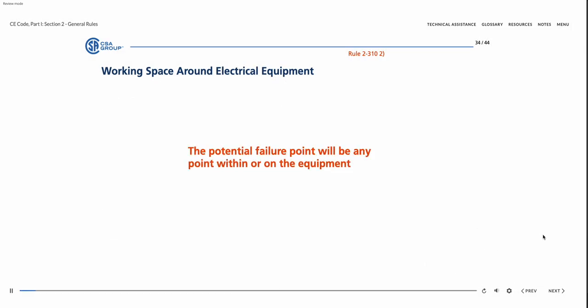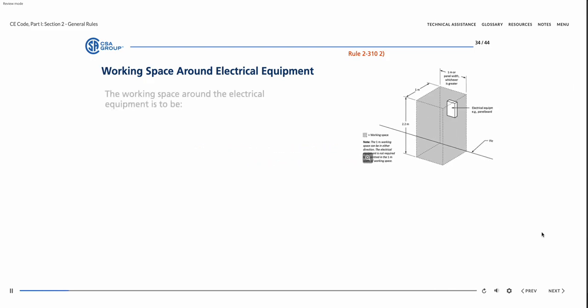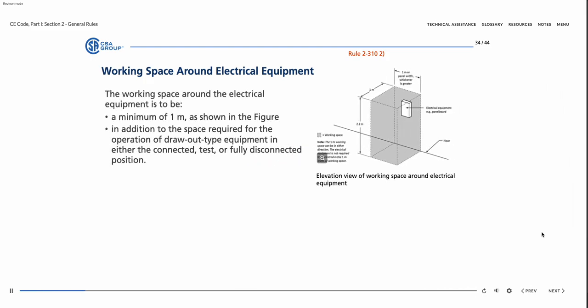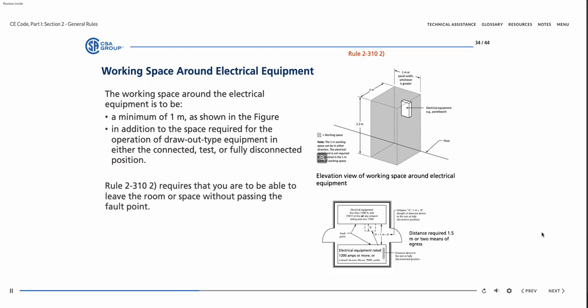The potential failure point will be any point within or on the equipment. The working space around the electrical equipment is to be a minimum of 1 meter, as shown in the figure, and is to be in addition to the space required for the operation of draw-out type equipment in either the connected, test, or fully disconnected position.